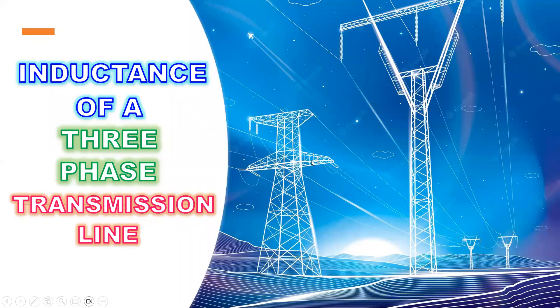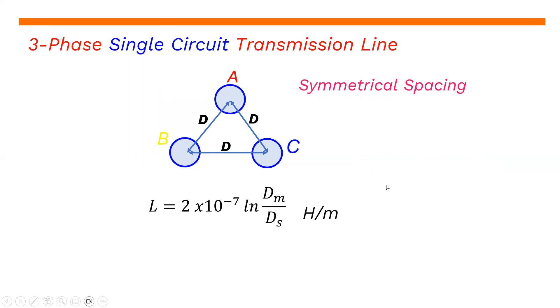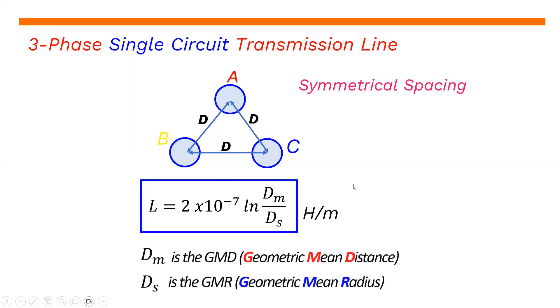Today we're going to talk about the inductance of a three-phase transmission line. We have here a three-phase single-circuit transmission line with symmetrical spacing. The inductance can be expressed as L = 2 × 10⁻⁷ × ln(D_M / D_S) Henry per meter, where D_M is the geometric mean distance (GMD) and D_S is the geometric mean radius (GMR).